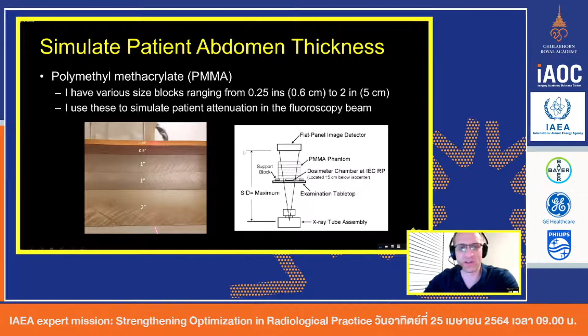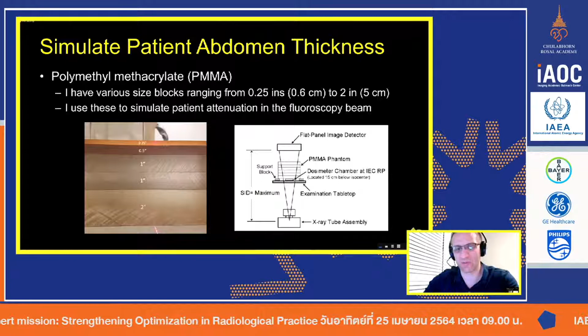So we definitely use this when we're trying to estimate how image quality will change by different patient size. And of course, when it comes to radiation, when you put an ion chamber or some kind of dose monitoring device in there, the system will change the radiation output based on the various different thicknesses of plastic. And so the question was, how many of these blocks should I use to simulate various different patients? And here is a table for those of you. So this is in the PDF that will go out. Of course, you can have this and look at it closely.